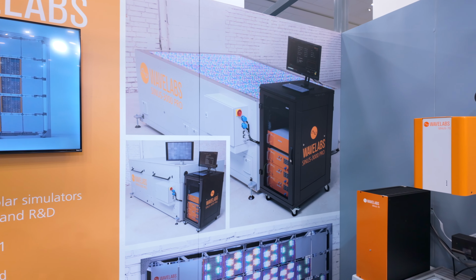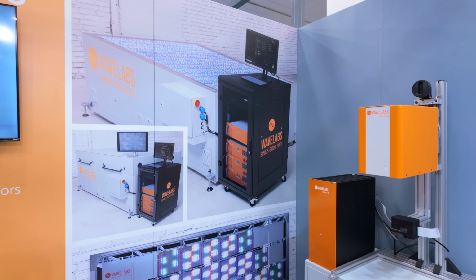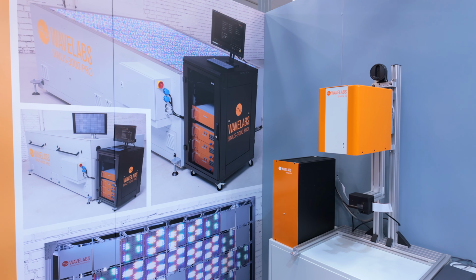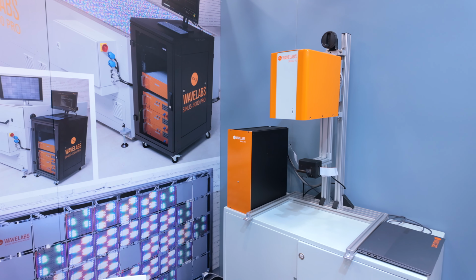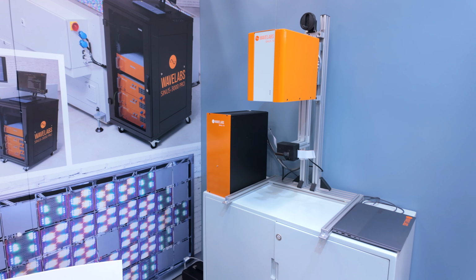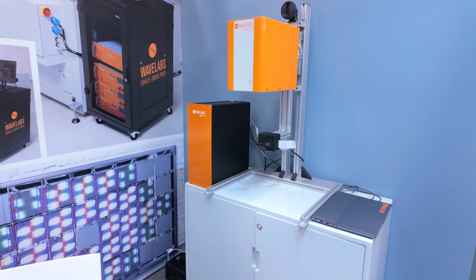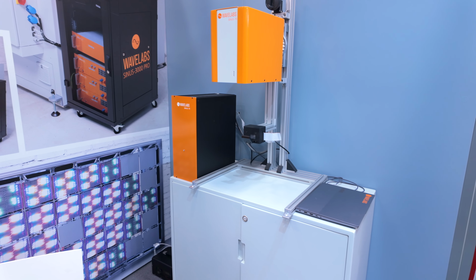One of the requirements, it's an IEC standard, is to be able to do a performance test on a solar module and get the nameplate rating. So the way that you determine the power to sell your product, you need to use one of these systems to test that indoors. The big metrics that come out are peak wattage of the modules, but also module efficiency. Less so module efficiency, but more solar cell efficiency is important. But these are kind of benchmark tests that every manufacturer requires. So it's kind of a necessity in the industry.